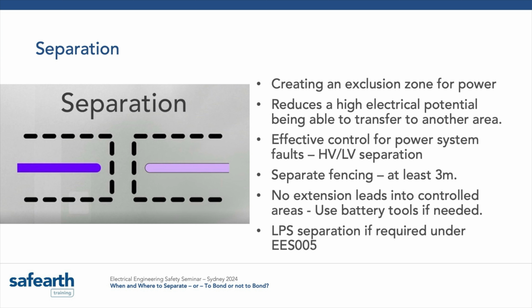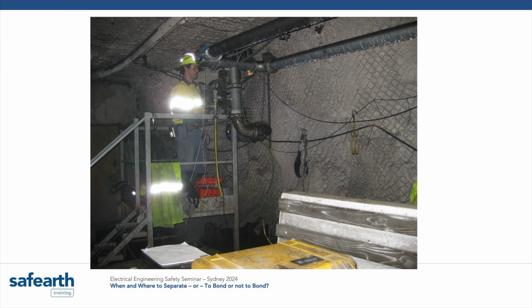Whereas with a common earth system in a distribution transformer, any earth fault you have on the primary side will see the neutral and will lift the entire system. So for example, bathhouses on our mine sites, you might choose or want to have a separately earthed HV/LV supply supplying that bathhouse. I guarantee you a well-designed separately earthed system will produce lower volts on the neutral more often. That's just how they work. I've got another image later, which I really should have put after this one to talk about separation, but when I come to it, I'll remind us of it.